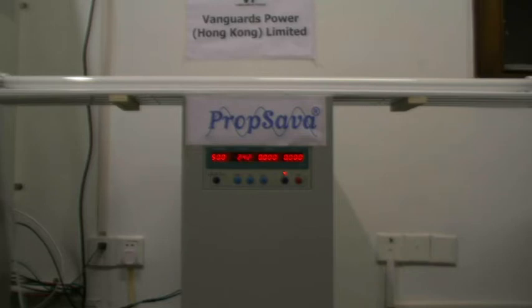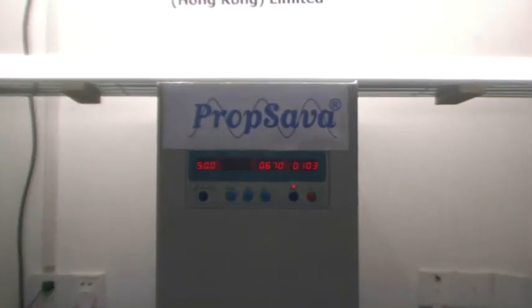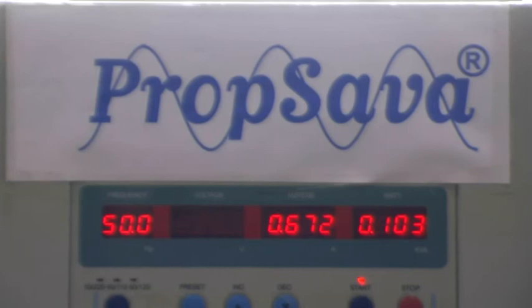I'm now going to switch the electronic fluorescent lights on and we're going to have a look at one of our workshop PropSava units running and controlling the voltage on this load today. You'll notice the current voltage supply to the electronic ballast fluorescence. At 242 volts — an average voltage for the UK — these particular lights are pulling 0.675 amps and 103 to 104 watts.